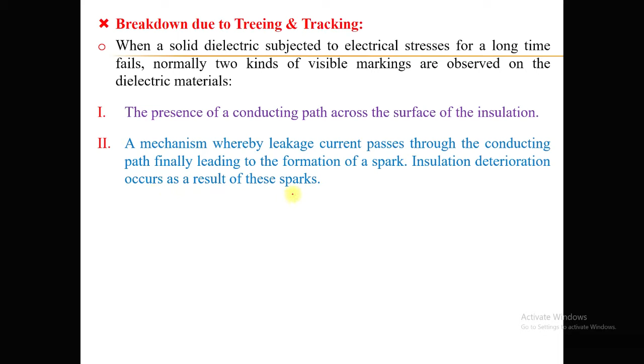By considering that fact, the dielectric material may fail due to the presence of these conducting paths. When it is under electrical stresses of lower value over a longer life of its operation and then fails, when you closely examine it, you always observe these two markings. One is the presence of a conducting path across the surface of the insulation, and these paths generally indicate the path through which the leakage current is continuously passing. So what does it exactly cause? It will cause the deterioration of the insulation, and at the end it will rupture.